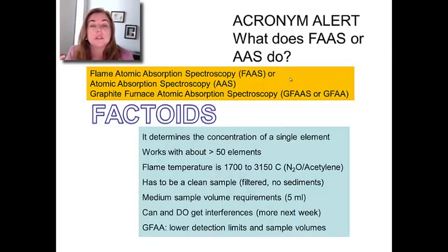The problem is some materials will oxidize. If you have an iron atom in an air flame, the oxygen can combine with the iron and make an oxide, which can introduce problems. It might not go into the gas phase or have a different absorption spectrum. Nitrous oxide is another option with acetylene—it's more expensive but changes the flame in important ways. Your sample has to be clean, not cloudy. You have to do total digestions, and you need a fair bit of sample volume.